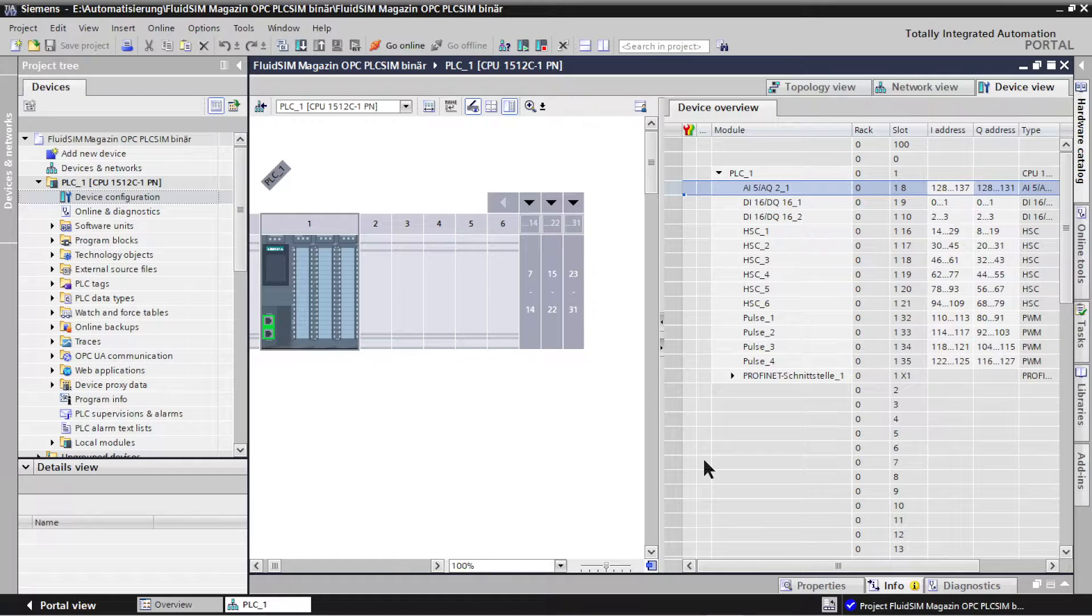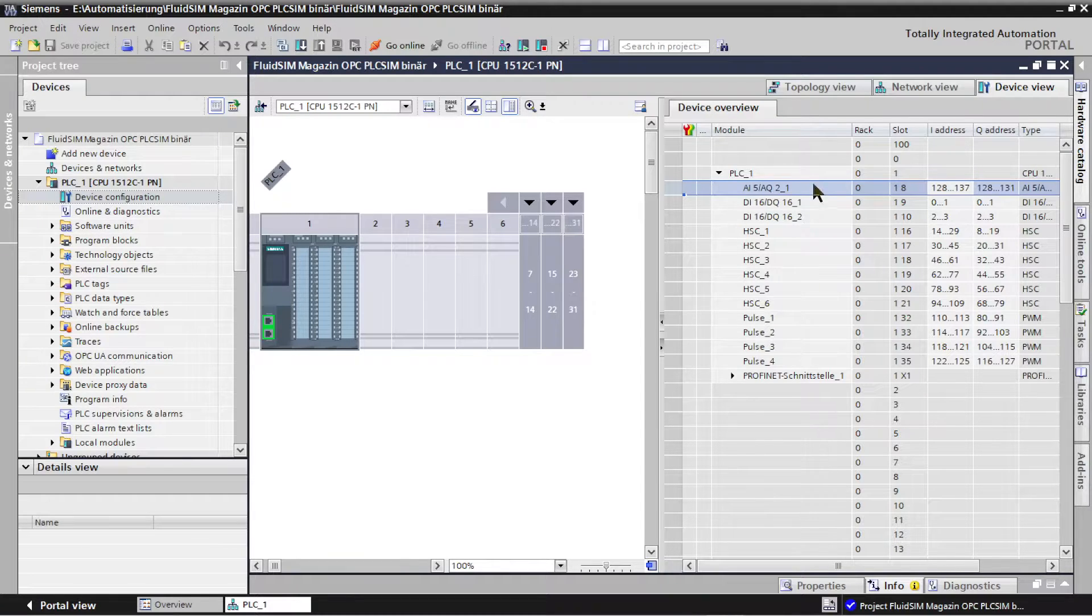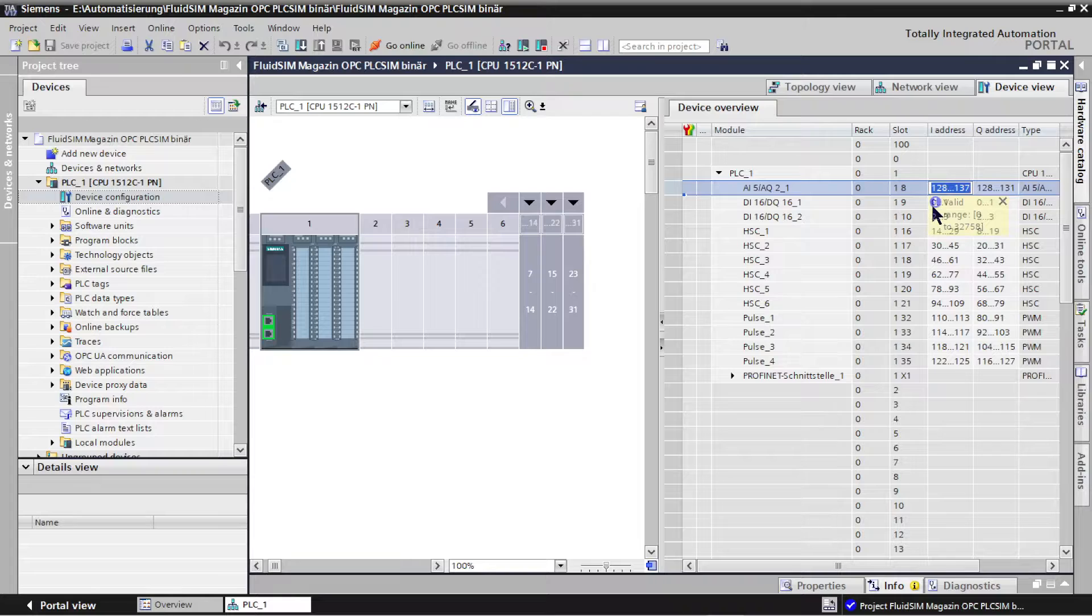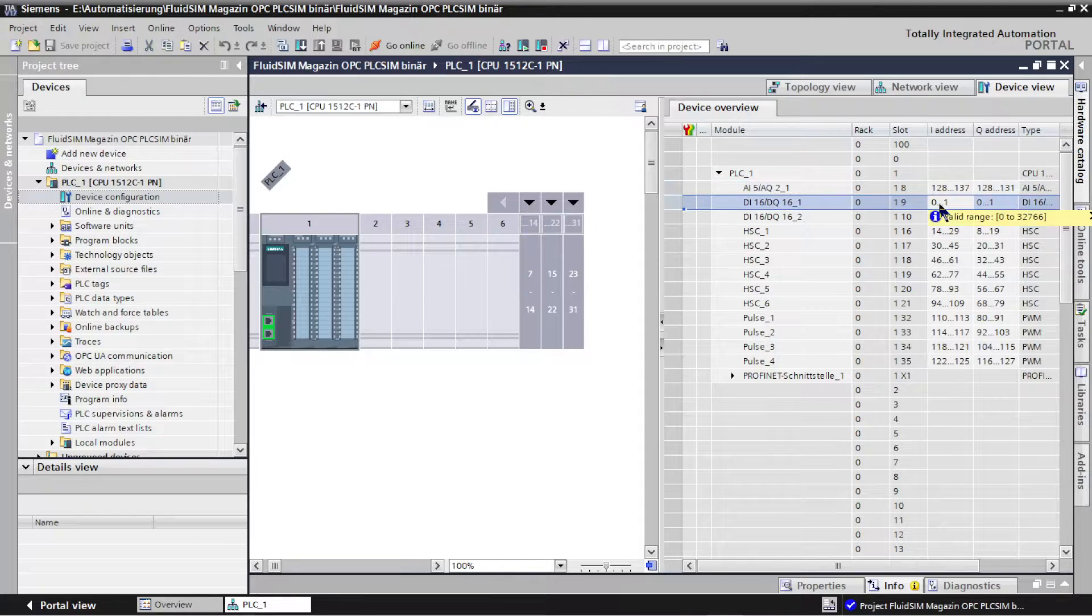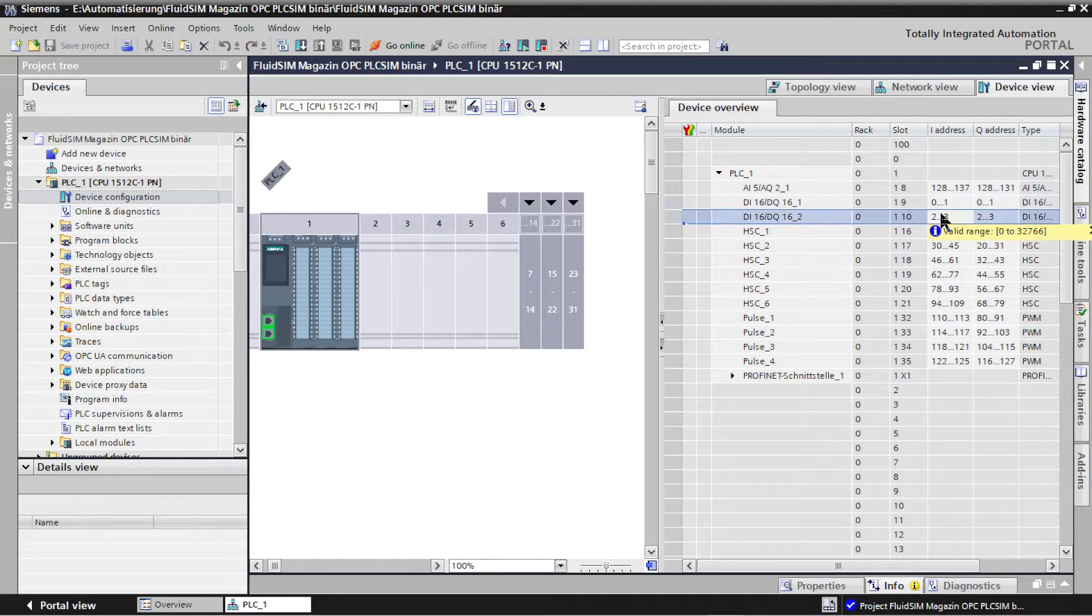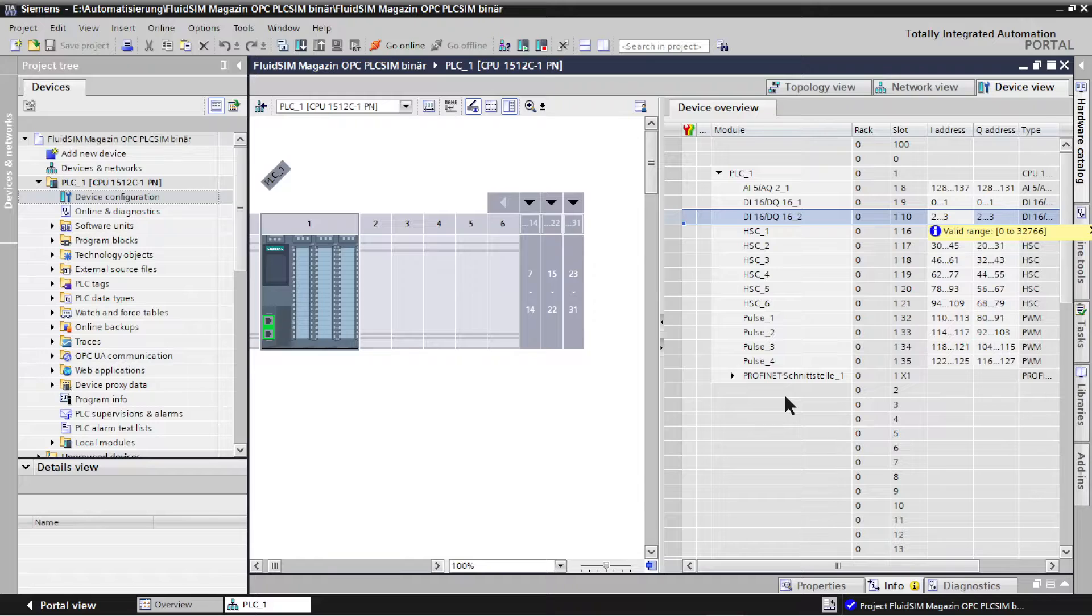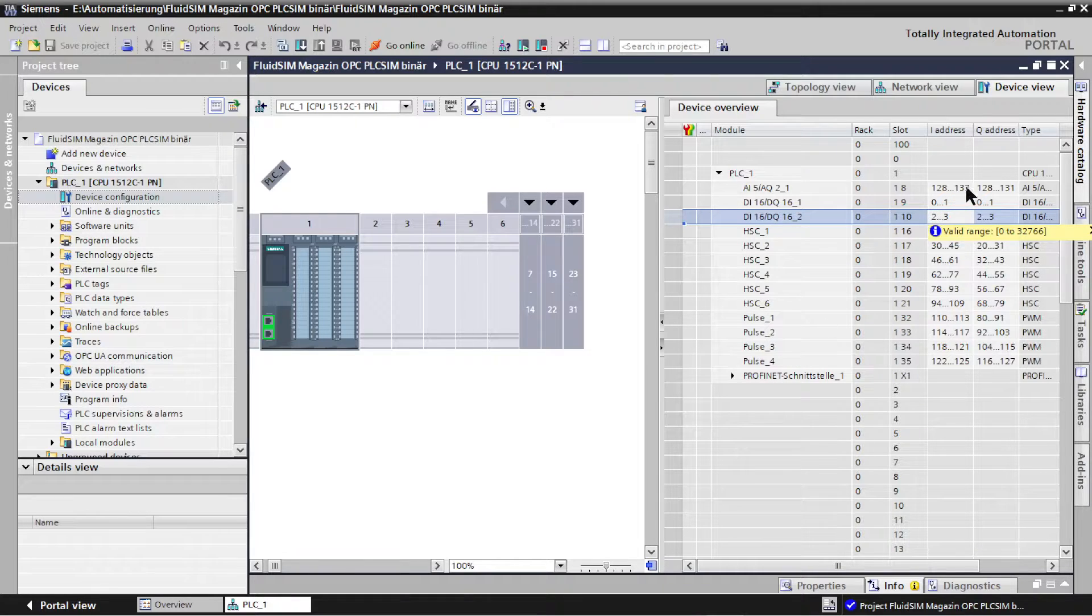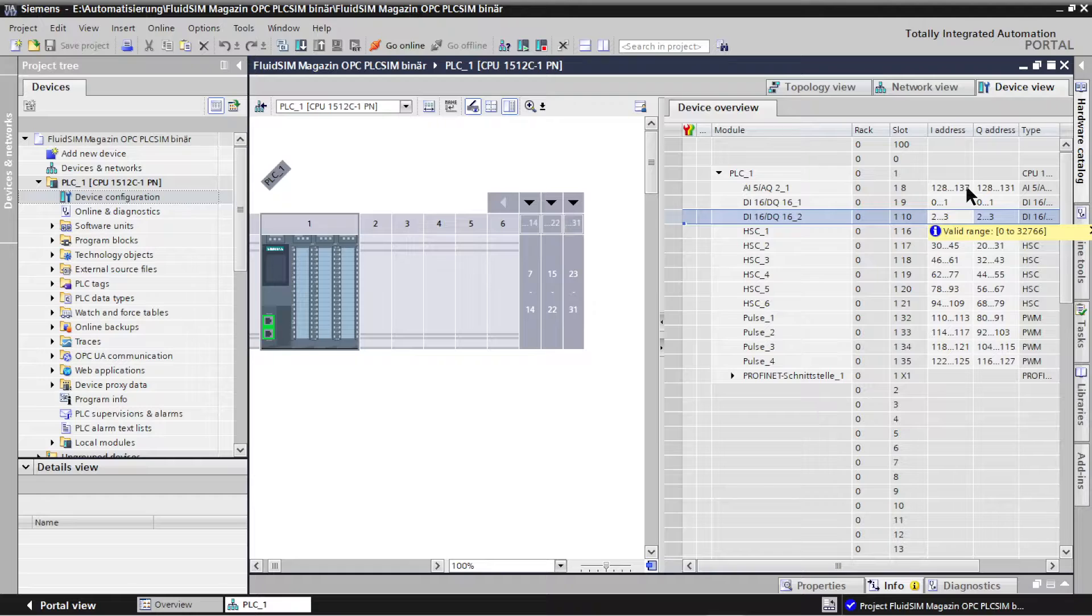Here you could also change the IO addresses for binary and analog inputs and outputs. In the example they have been set to the address bytes of the binary IO at 0 to 3 and the analog IO at 128 to 137.